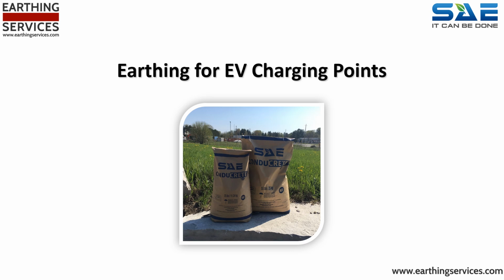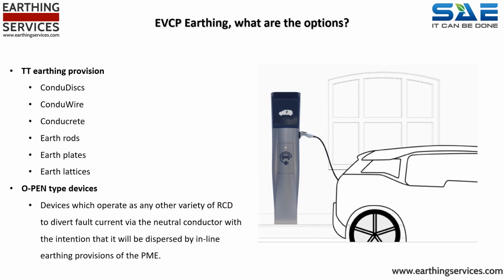We will now consider earthing for EV charging points. There are many different options for EV CP earthing. TT earthing provisions, including ConduDiscs, ConduWire, Conducrete, earth rods, earth plates, and earth lattices, O-PEN type devices, which operate as any other variety of RCD to divert fault current via the neutral conductor with the intention that it will be dispersed by inline earthing provisions of the PME.